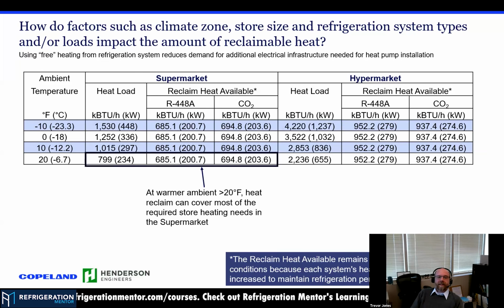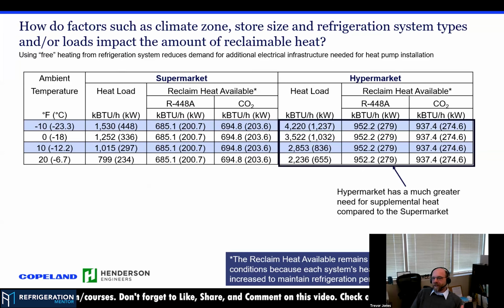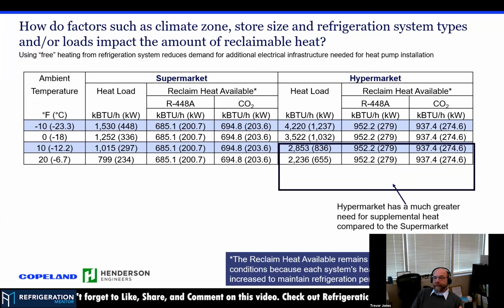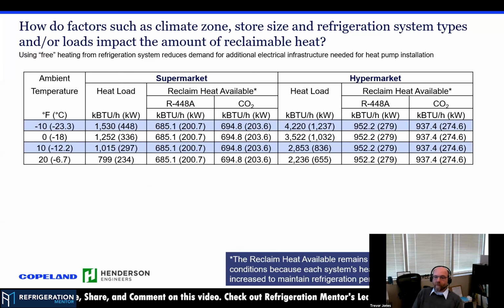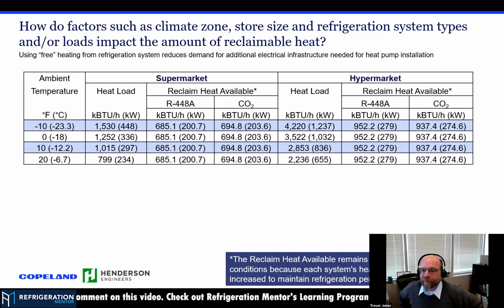So looking at this, for the supermarket we're at a balance point at around 20 degrees, where there's almost enough heat to cover the heating load from just reclaim. For our hypermarket, you're almost at around 55 degrees, so a lot more supplemental heat was going into the hypermarket design. So what you mean there is that with the compressors running at 20 degrees Fahrenheit, or -6 Celsius, that's the ambient outside, you're only generating about half that heat through the heat reclaim. So we need the other 50% through some sort of auxiliary heat, correct? Correct.